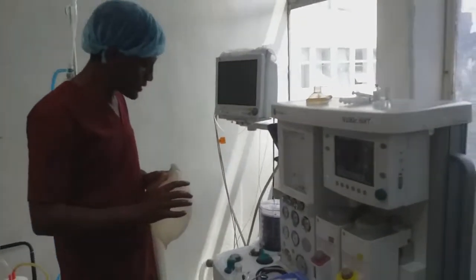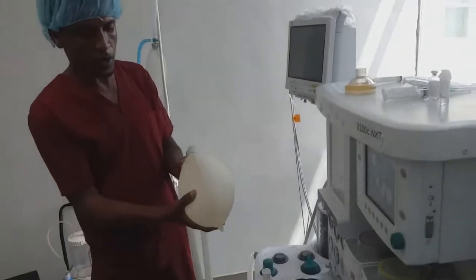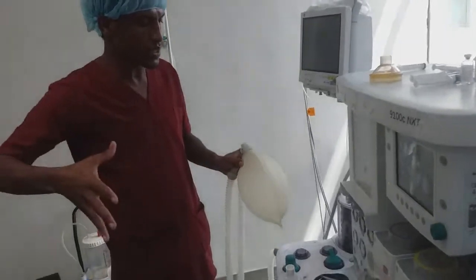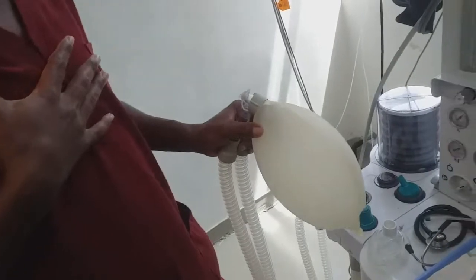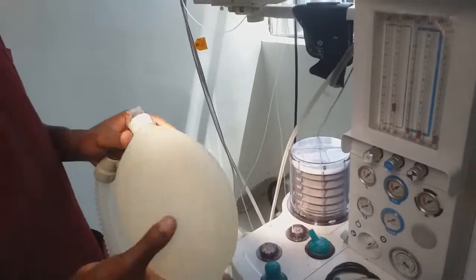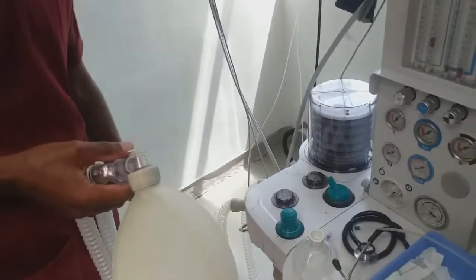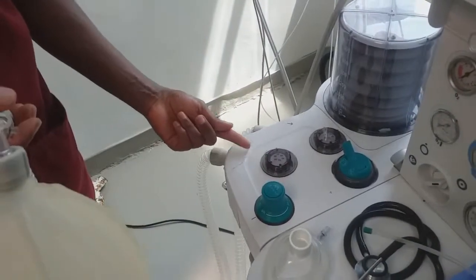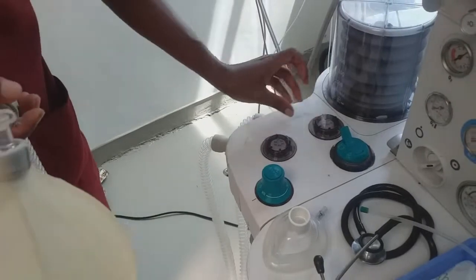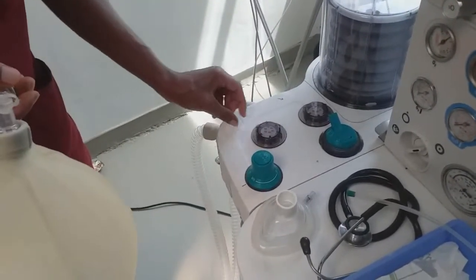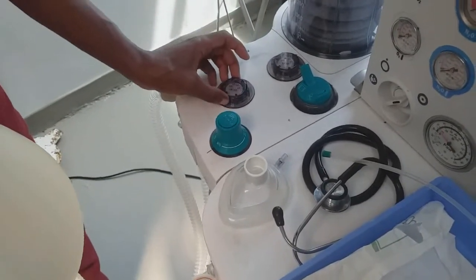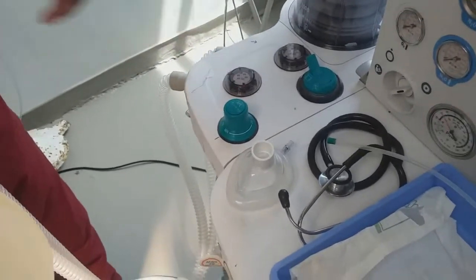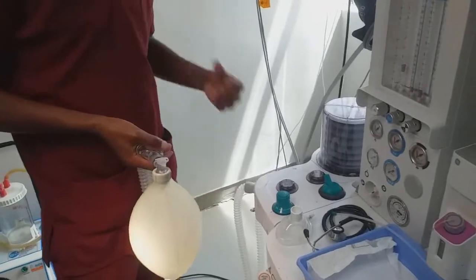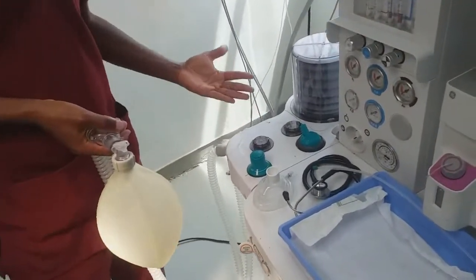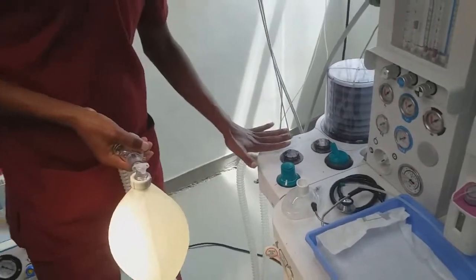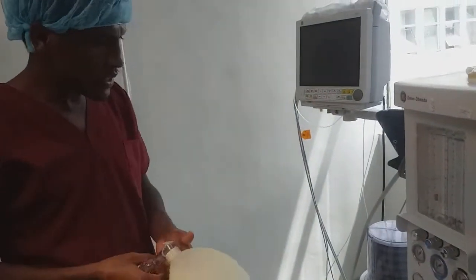In this ventilation lung test, we need to assume that this is the lung of the patient. Then there is the compliance of the bag as the lung of the patient. And in this ventilation system, we also need to observe the configuration of the system. There is the expiratory limb, this is the inspiratory limb. This is one unidirectional valve. During this, the unidirectional inspiratory valve rises up when the patient takes in oxygen. When the patient breathes in, this rises up, and when the patient expires, this will depress down. This indicates the configuration of the system.